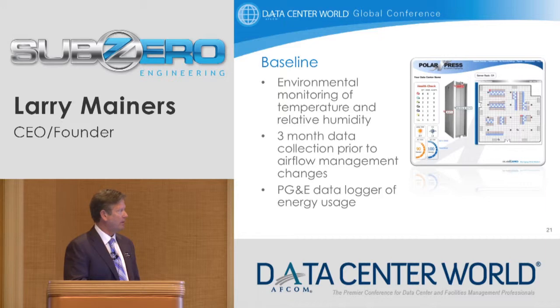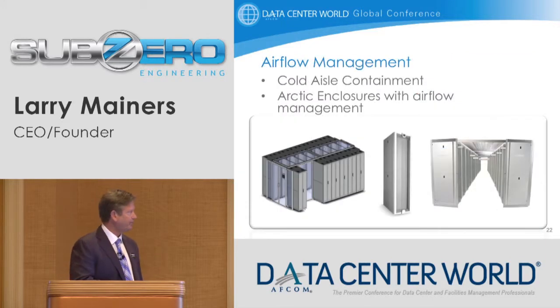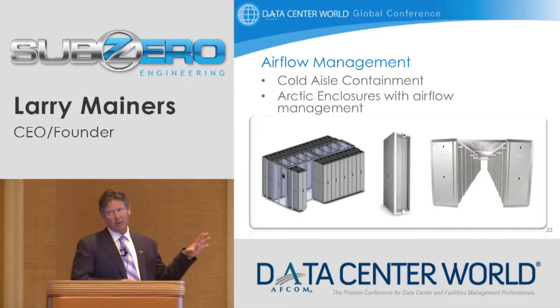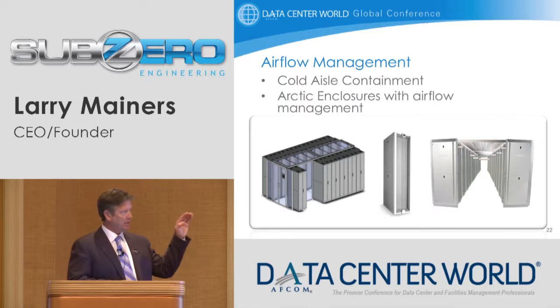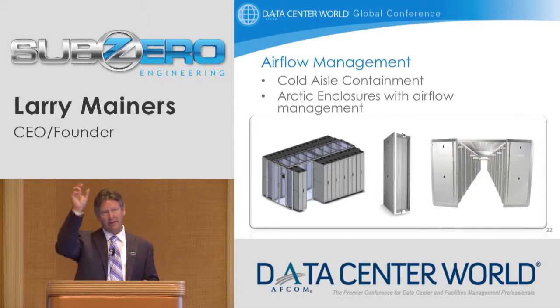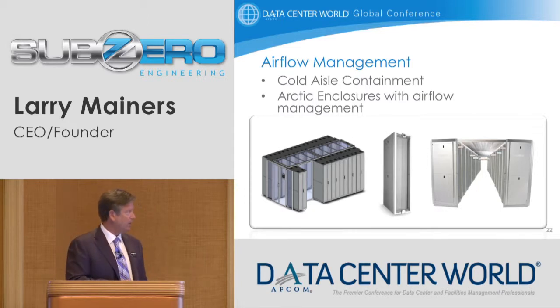That's an example graphic of looking at the IT intake, whether it's temperature, relative humidity, or pressure in the area, monitored through the baseline and through the installation. In a typical containment installation, you require far fewer sensors. For example, in a cold aisle containment, there's typically only a 1 degree difference between the bottom and top of the cabinet, and one aisle end to the other. So having a top, middle, and bottom sensor at every third cabinet isn't typically required. You can do far fewer sensors in an airflow containment.